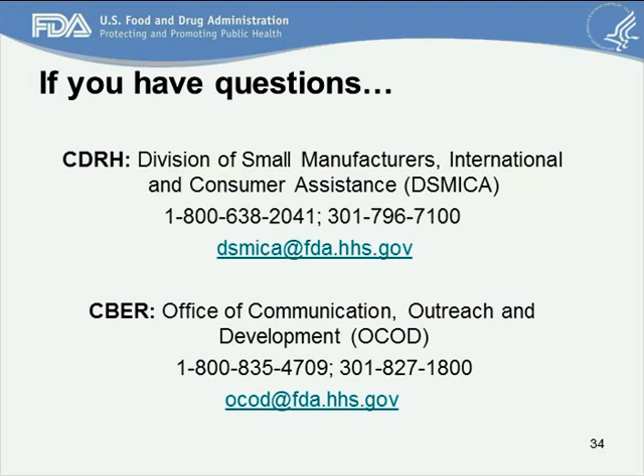If you refer to the guidance that Elizabeth outlined called Early Collaboration Meetings under the FDA Modernization Act, Final Guidance for Industry and for CDRH staff, which was issued in 2001, that provides more specific information about agreement and determination meetings. But they have more specific procedures, different timelines, and less opportunity for interactive discussion that's allowed under the pre-sub program.